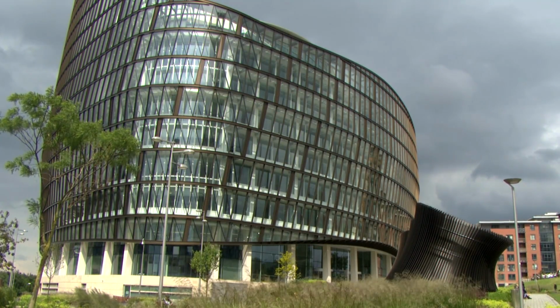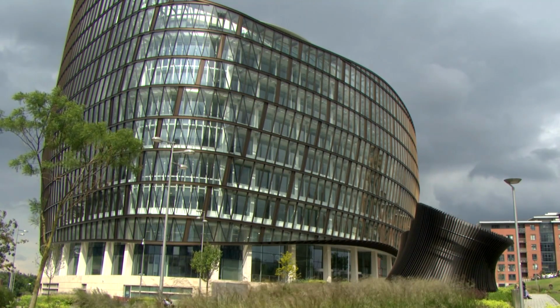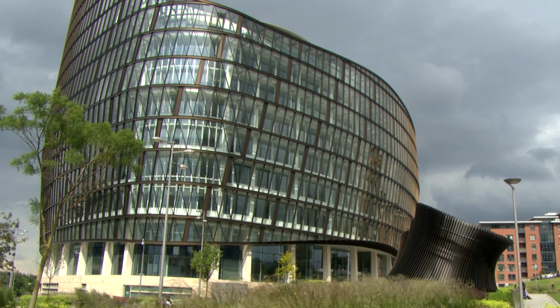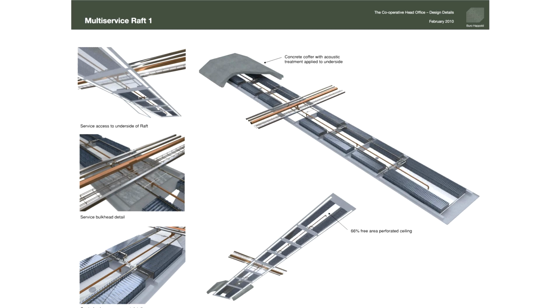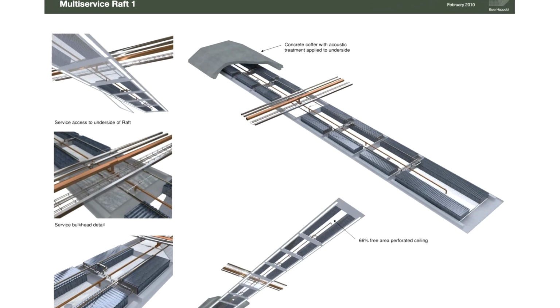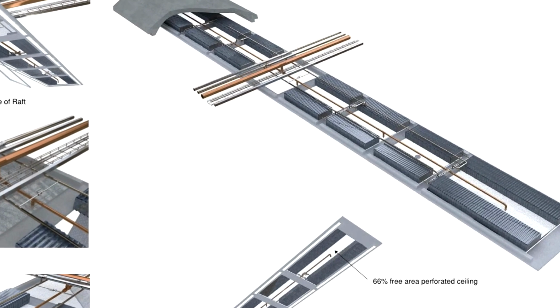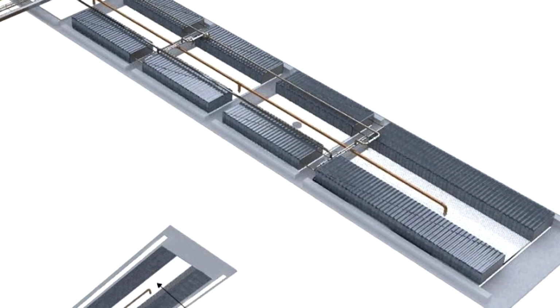Another decision that has made a difference is the specification of passive chilled beams rather than traditional fan coil units, or FCUs. There are 2 types of chill beams. One's active, where you blow air through it to increase the amount of cooling. The other one is passive. So these are passive chill beams. And put simply, they're a copper coil wrapped around a pressed metal ceiling plate. And how they work is they absorb the heat from the occupants, from the PCs and various other heat-giving equipment on the floor space. So they absorb the heat, take it away, dispel it out the building, and then bring back chilled water.